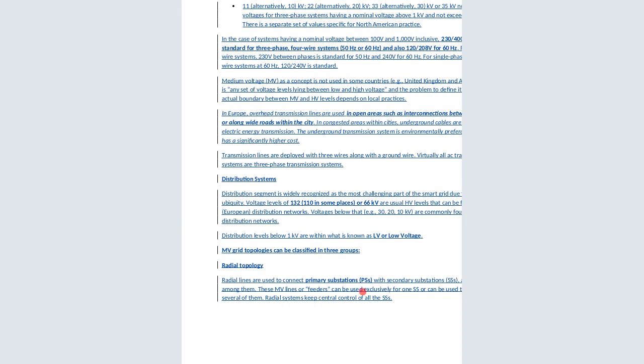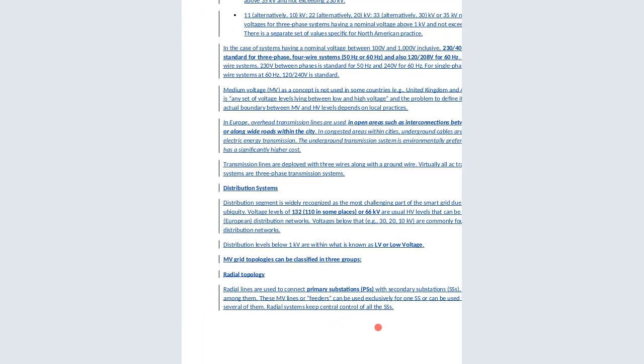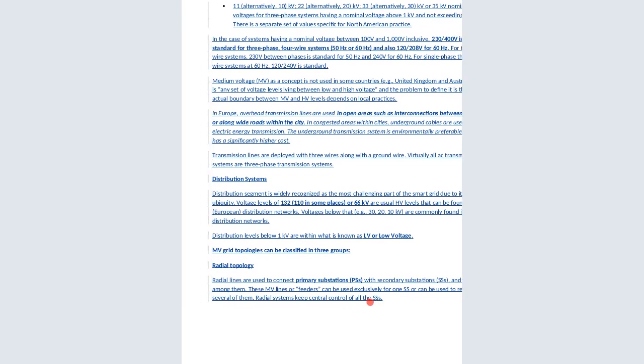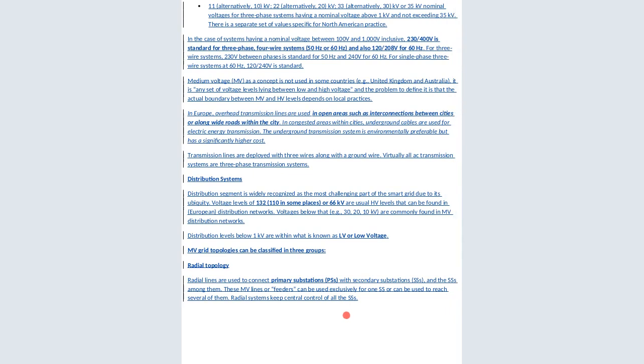And now we have different topologies. We have the radial topology. Radial lines are used to connect primary substations, that is PS, with the secondary substations, and the secondary substations among themselves. The MV lines, that is the feeder, will be used exclusively for one substation or can be used to reach several of them.